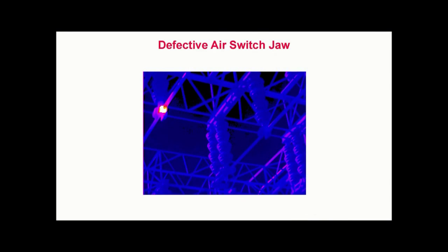Defective air switch jaw. This is a thermogram recorded in a large outdoor electrical substation. We are standing on the ground observing two phases of a three phase overhead disconnect switch approximately 30 feet above us. In this thermogram, we see a hot area indicated as white in the contact area of the left pole of the switch.